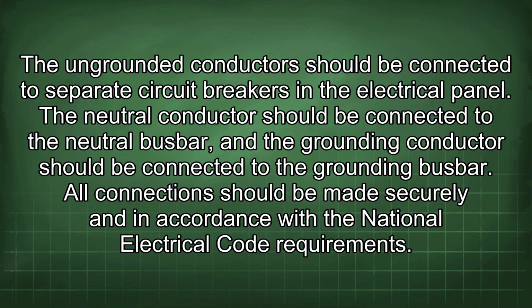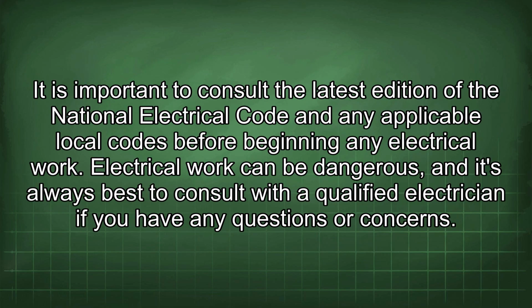The ungrounded conductors should be connected to separate circuit breakers in the electrical panel. The neutral conductor should be connected to the neutral busbar, and the grounding conductor should be connected to the grounding busbar. All connections should be made securely and in accordance with the National Electrical Code requirements. It is important to consult the latest edition of the National Electrical Code and any applicable local codes before beginning any electrical work. Electrical work can be dangerous, and it's always best to consult with a qualified electrician if you have any questions or concerns.